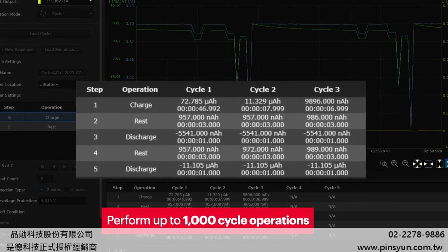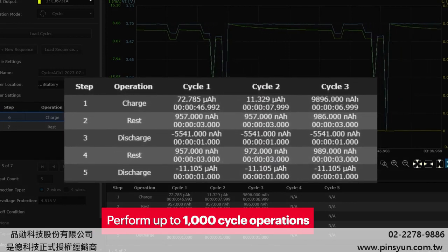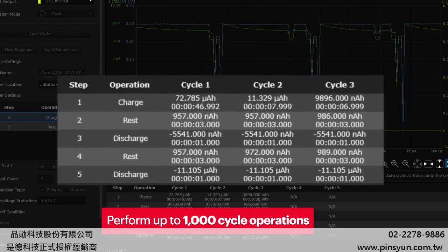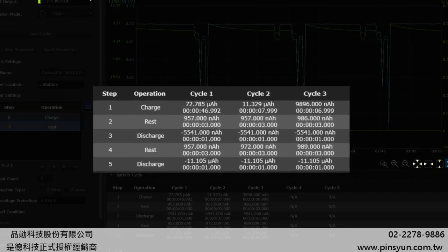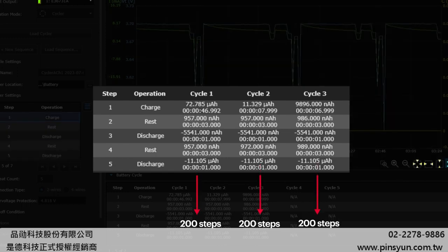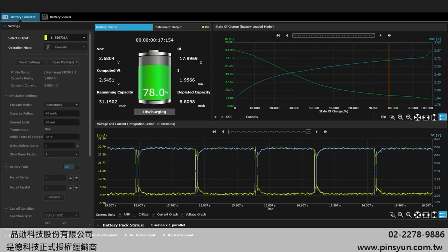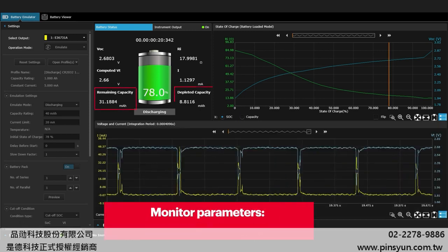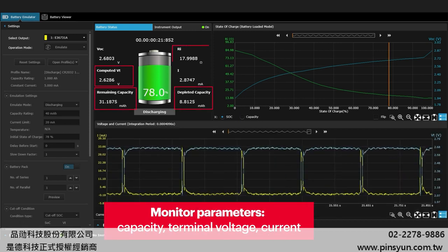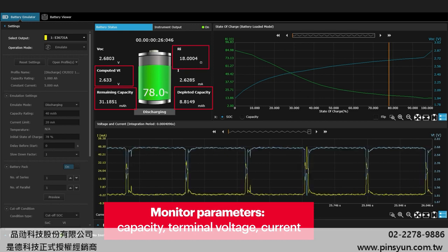You can perform up to 1,000 cycle operations on the battery to determine the effect of aging and evaluate the battery's reliability. Each cycle could have up to 200 charge-discharge steps. With the battery emulation software, you will be able to monitor the battery's vital parameters such as capacity, terminal voltage, current, and time to gain a detailed insight into your battery life cycle.